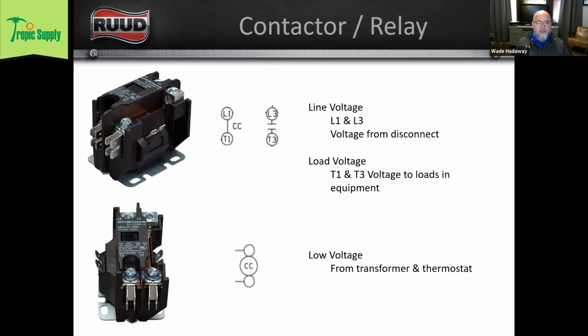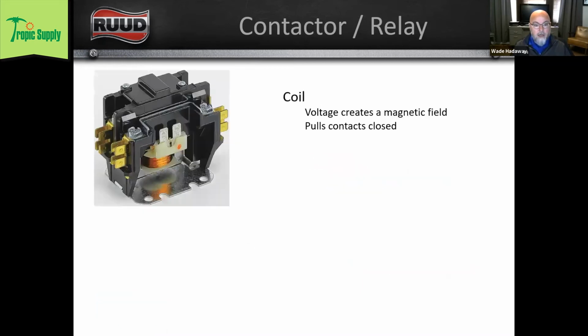All right, so contactors and relays. I mentioned earlier that contactors and relays and sequencers and other components have both line voltage and low voltage, or line voltage and control voltage. And we're wiring our line voltage from our disconnect to L1 and L3. And then our load voltage is T1 and T3, and that's going to the loads in the piece of equipment. And then we've got our low voltage side, which is coming from our transformer through our thermostat to our outdoor unit. And that's going to energize that coil. So contactors and relays, they're really very similar. Typically, contactors have a higher rating, and they can handle more current and more voltage than a relay can. But it's all dependent on what we're working on, right?